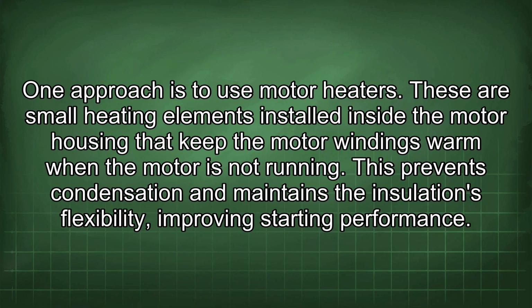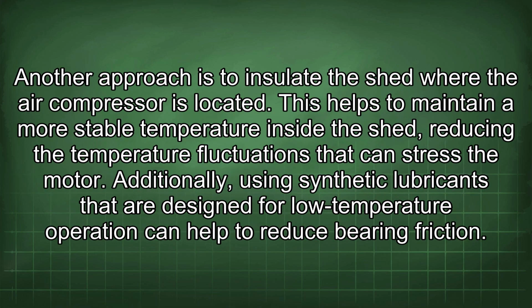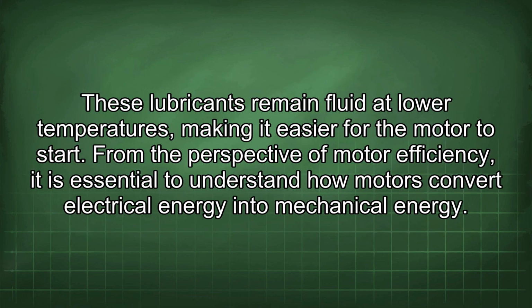One approach is to use motor heaters. These are small heating elements installed inside the motor housing that keep the motor windings warm when the motor is not running. This prevents condensation and maintains the insulation's flexibility, improving starting performance. Another approach is to insulate the shed where the air compressor is located. This helps to maintain a more stable temperature inside the shed, reducing the temperature fluctuations that can stress the motor. Additionally, using synthetic lubricants that are designed for low temperature operation can help to reduce bearing friction. These lubricants remain fluid at lower temperatures, making it easier for the motor to start.